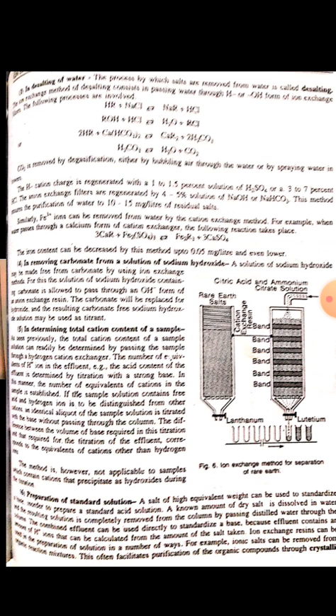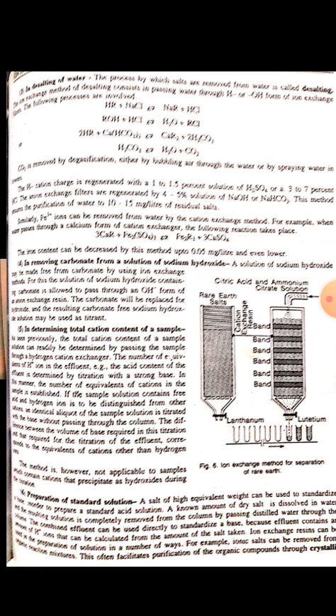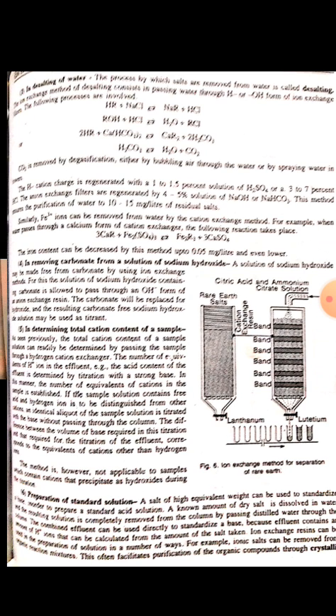The hydrogen cation charge is regenerated with a 1 to 1.5% solution of sulfuric acid or a 3 to 7% solution of hydrogen chloride. The anion exchange filters are regenerated by 4 to 5% solution of sodium hydroxide or sodium bicarbonate. This method ensures the purification of water to 10 to 15 milligrams per liter of residual salts.